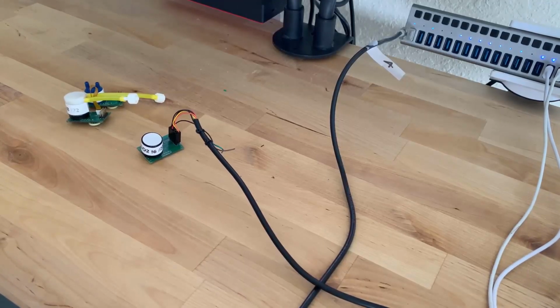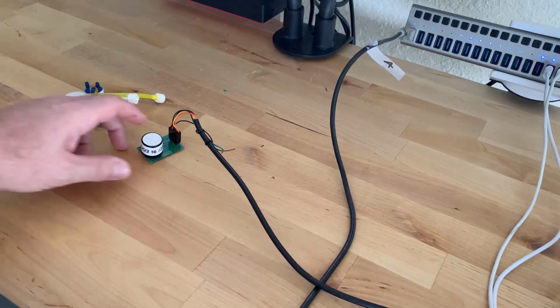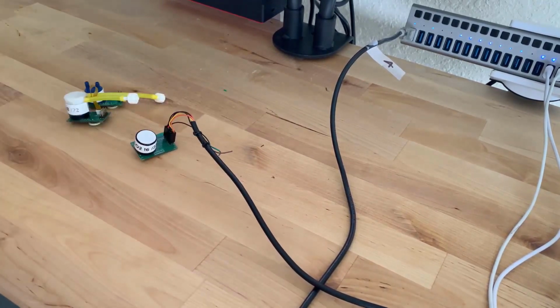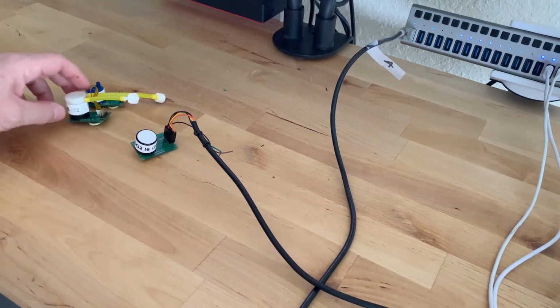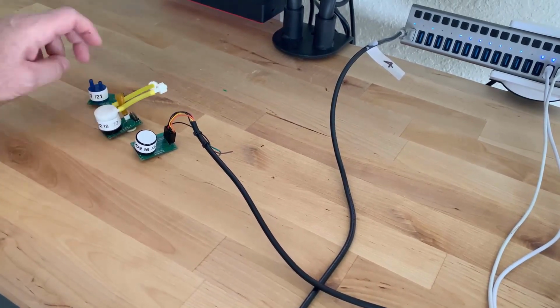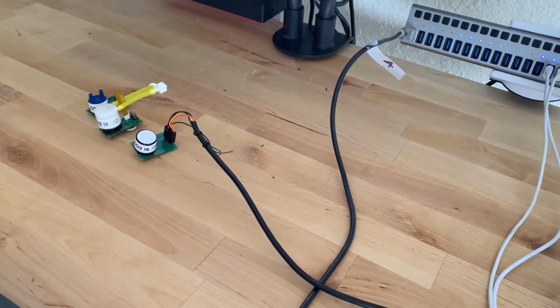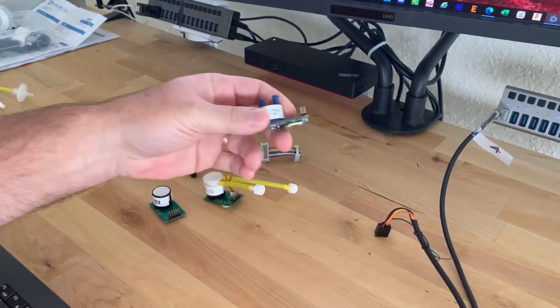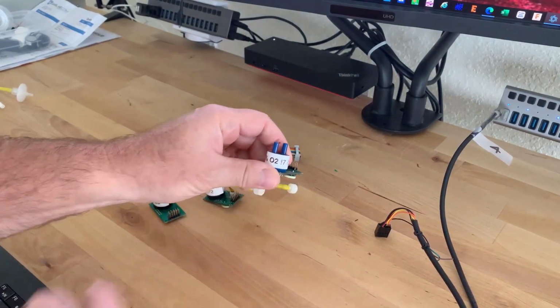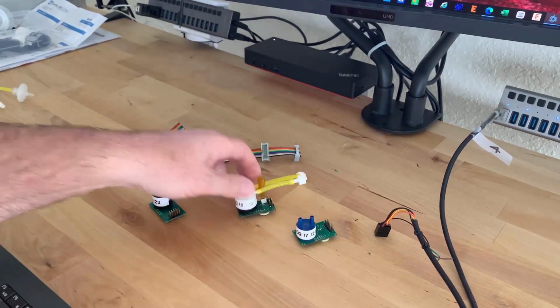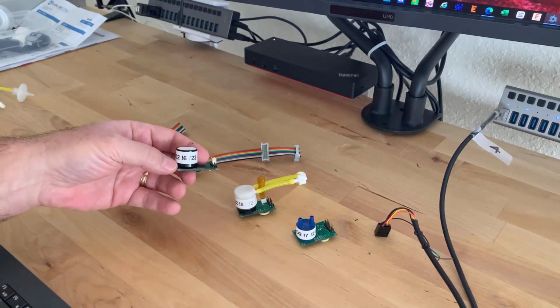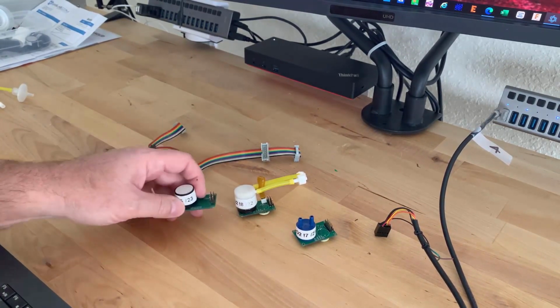We'll repeat the process with any of these other sensors here, and that's what we do to configure them. So each guy is going to have an address on them. All these sensors have already had addresses assigned. This happens to be an oxygen sensor, which has address 07. This is a CO2 with a tube cap, which happens to be 08. And this guy here is a 5% CO2 sensor and happens to be on address 6.